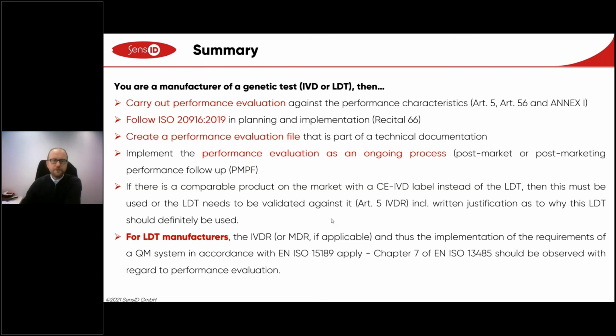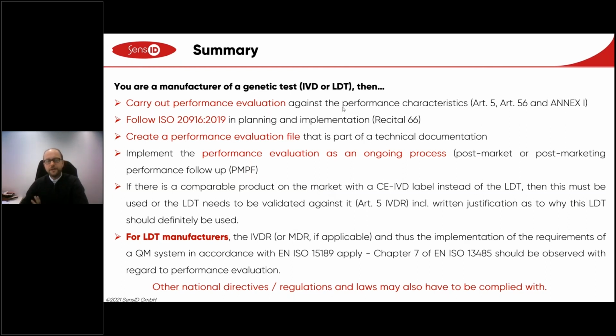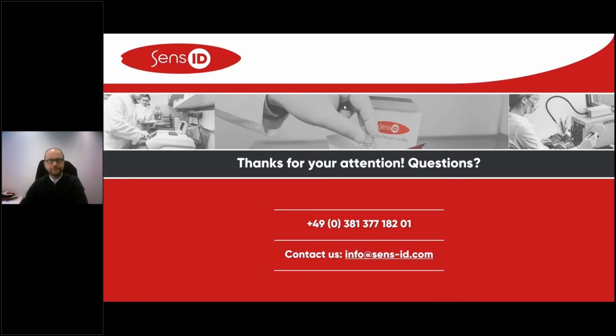So for LDT manufacturers, the IVDR or MDR, if applicable, and thus the implementation of the requirements of a QM system apply. And of course, also more or other national directives or regulations and laws may also have to be complied with. Like in Germany, for example, the RiliBÄK.